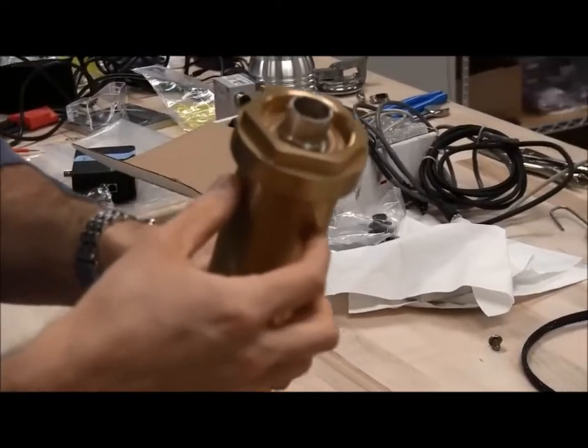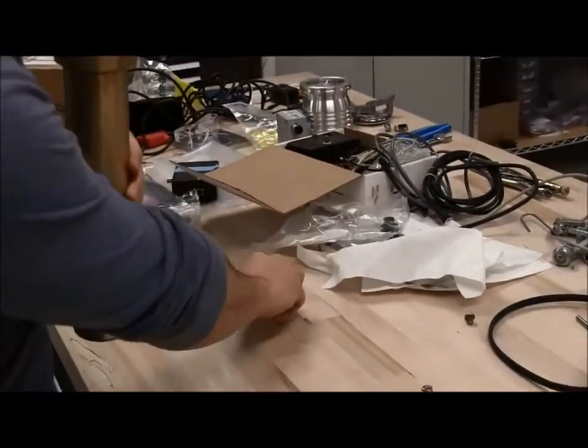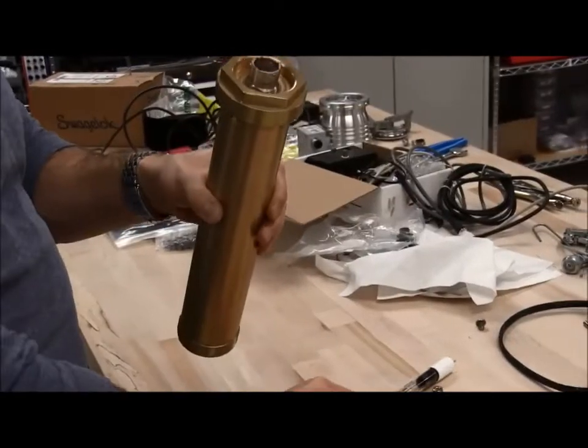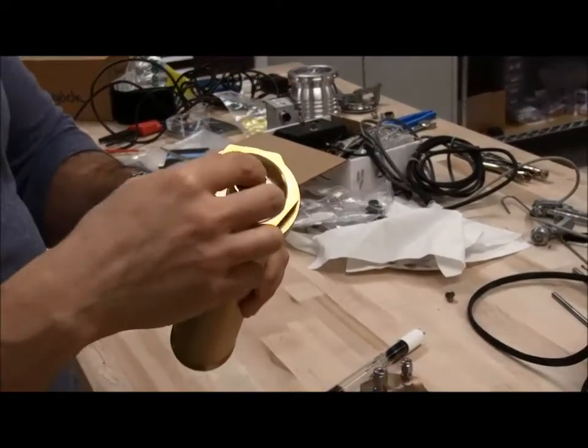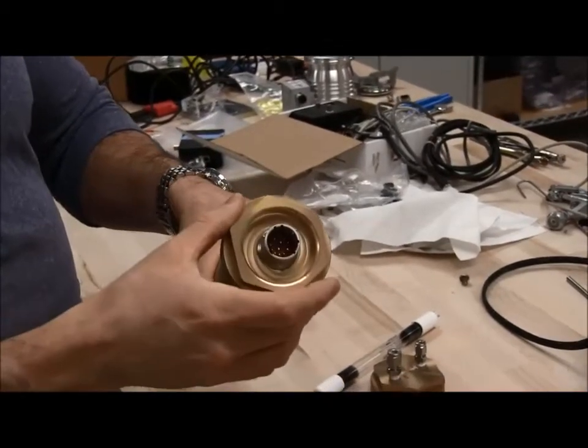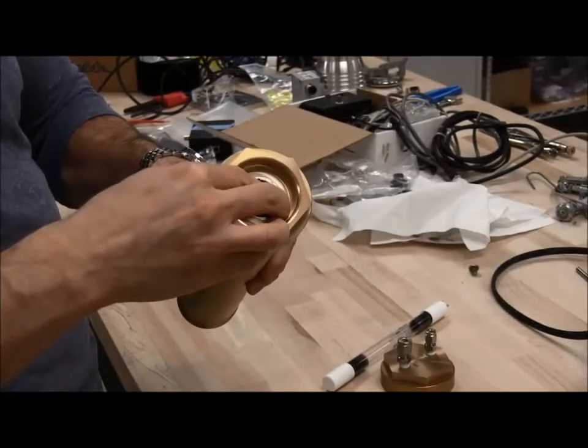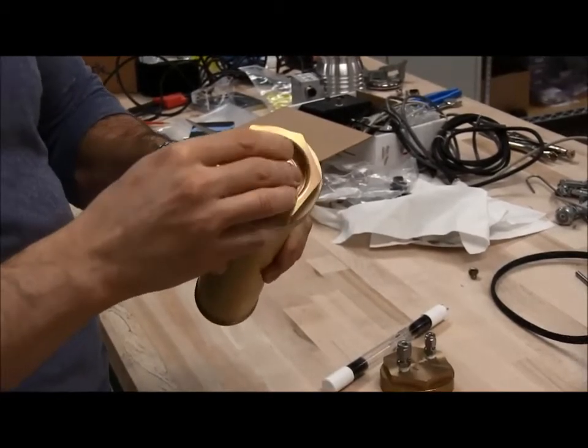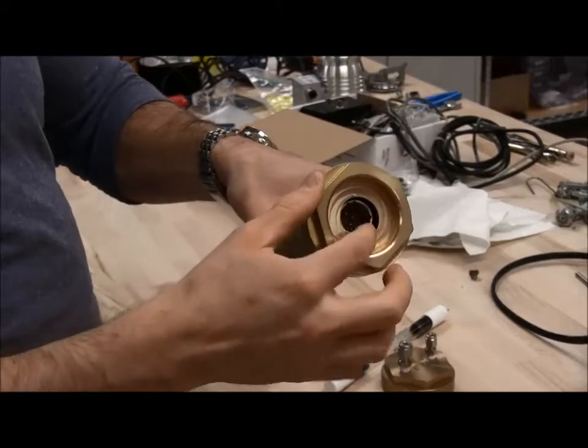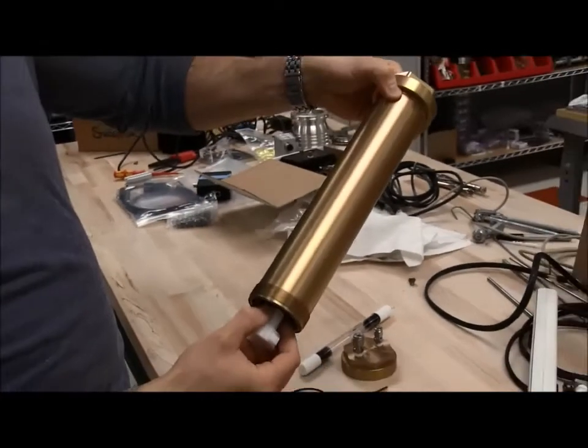So now because there's some copper wires on the inside that connect this connector to the top pins on the lamp, the most important part is to not twist those wires so they don't snap off. What you want to do is leave this top piece on, gently push down on the connector so that it's clear of the cutout on the plate, and then while you're pushing it, pull it out from the bottom.